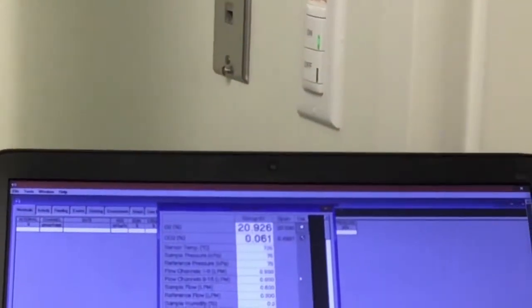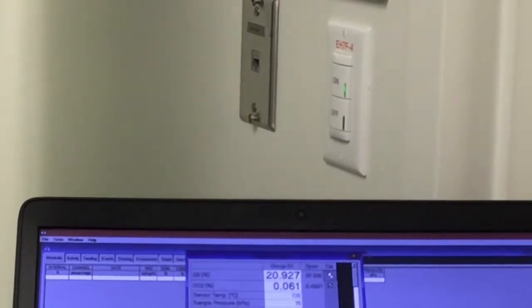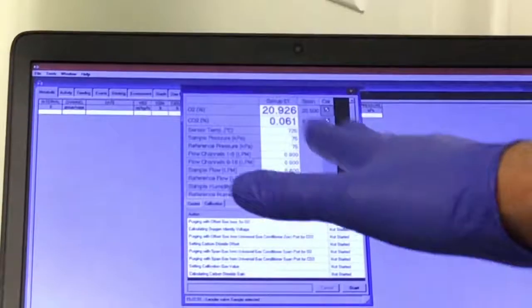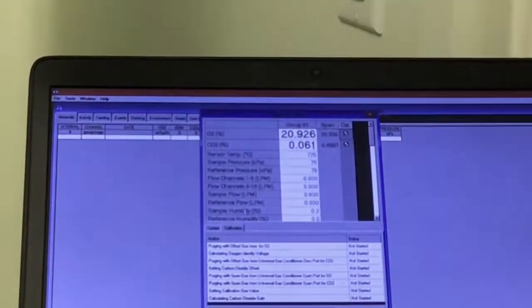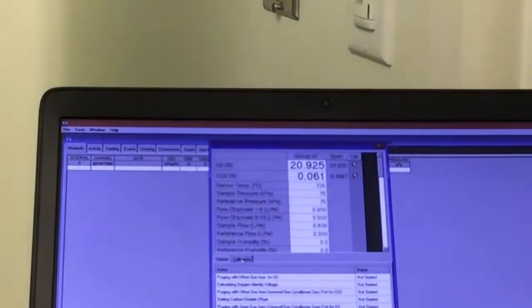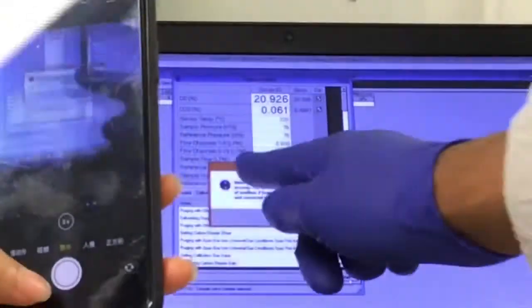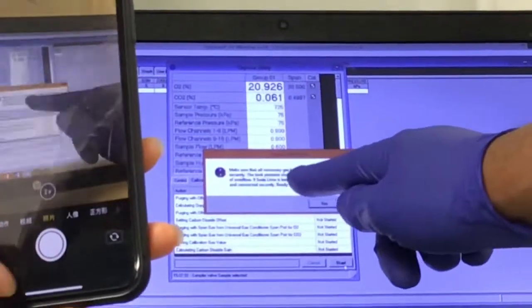So for calibration, there are 2 lines, O2 and CO2. You can do both. Whichever one is clicked is the one it's doing. Right now it will just do CO2. As you see, it removes the O2 steps. If I click it, it does both O2 and CO2, which is how I will tell you to do it. You click on calibration, and it will ask you to click on start calibration. We click start calibration. Make sure all the necessary gas tanks are turned on and plugged in.